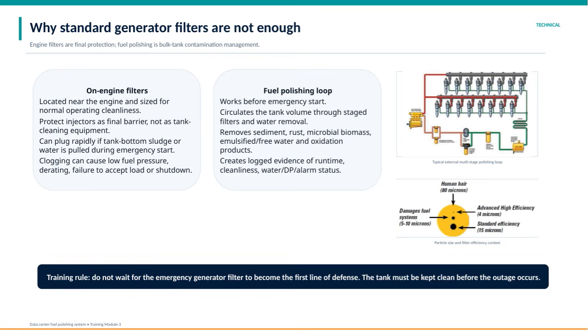When that happens, it can lead to low fuel pressure, reduced engine performance, or even a failure to accept load and a shutdown. That's where the fuel polishing loop comes into play. It operates before an emergency start by circulating fuel through a series of staged filters and water removal steps. This process removes contaminants such as sediment, rust, microbial growth, emulsified or free water, and oxidation products. Importantly, the system also logs runtime and cleanliness data, helping to track water levels, differential pressure, and alarms.